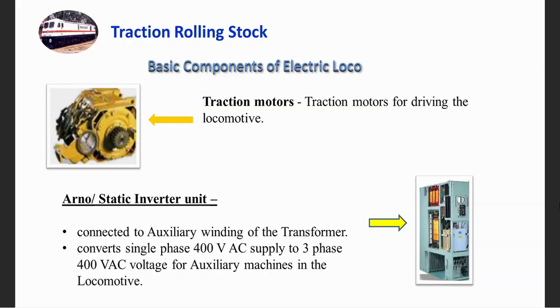The Arno, or static inverter unit, converts the auxiliary winding supply. It is connected to the auxiliary winding of the transformer, and converts single phase 440 volt or 400 volt AC supply to three phase AC supply, which is required for auxiliary machines in the locomotive. In the subsequent slide, I will explain the different auxiliary machines in the locomotive, and their role and function in the overall system.